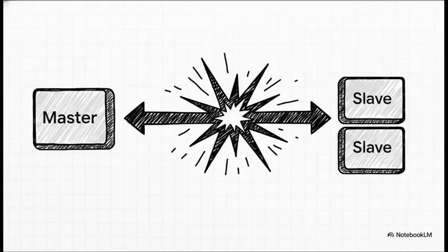So let's answer that question and summarize everything we've learned today. The absolutely most common failure? It's assigning duplicate slave addresses. Think about it. If two drives both have their ADD parameter set to 5, and the master asks 5 a question, both of those drives try to talk at the exact same time. It causes a massive bus collision, and boom, you get a total communication loss. So rule number 1, always ensure unique addresses.